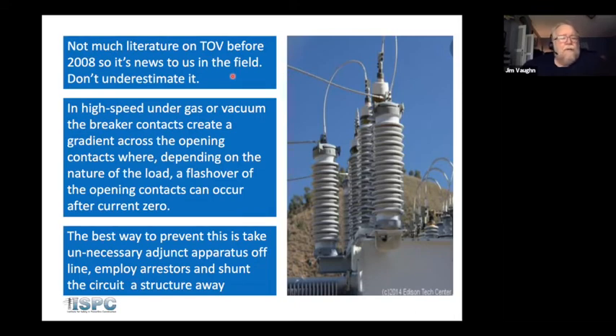High speed under gas or vacuum, the breaker contacts open, but when they open, they create a voltage gradient across the breaker. And here's one of the things that you may not also realize, and this is just one of the technical aspects. When a high-speed circuit breaker opens, the arc or the current doesn't actually interrupt until it hits zero in the waveform. And each one of the phases hits zero at a different time. So technically, at the speed of light, one phase will open before the other two do. And we end up with a gradient being created, a voltage gradient across the gap.